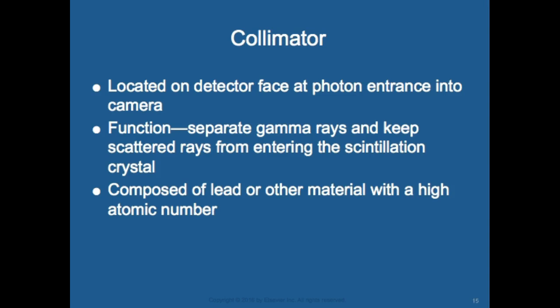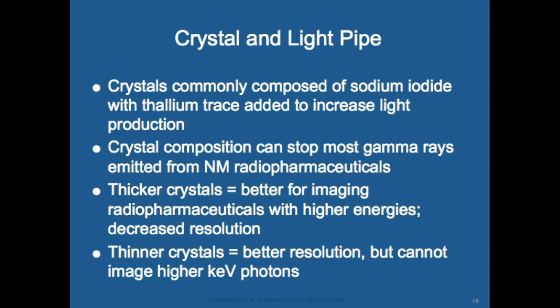The collimator's function is to separate gamma rays and keep scatter rays from entering the detector — just like in other imaging, they want to remove scatter rays from the diagnostic data. It is composed of lead or other high atomic number material.